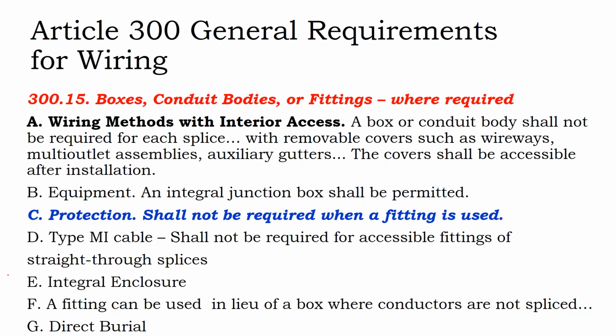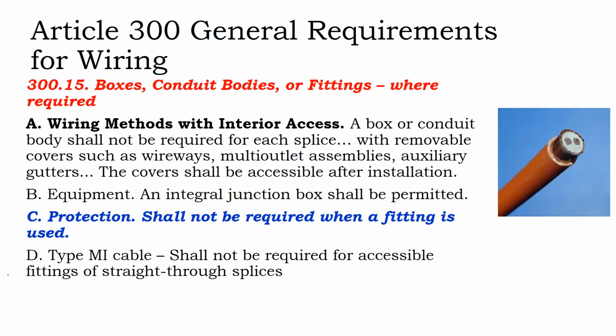So if you're using auxiliary gutters, you don't need to put a box inside of that. Then we get into physical protection. And what I want to point out, there is a cable type called MI, and then there's MC as well, where you buy super expensive cable, but some of that expense is in making the cable more robust. And so by buying a cable that is metal clad, you might fulfill a requirement for MC cable being inside a metal enclosure.